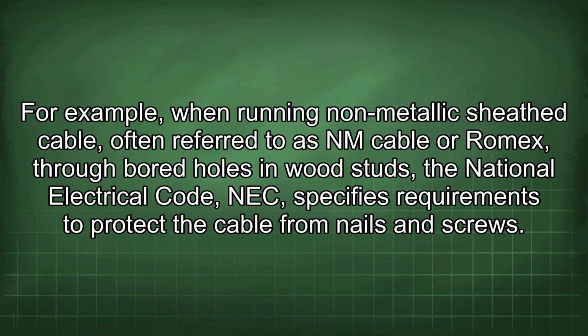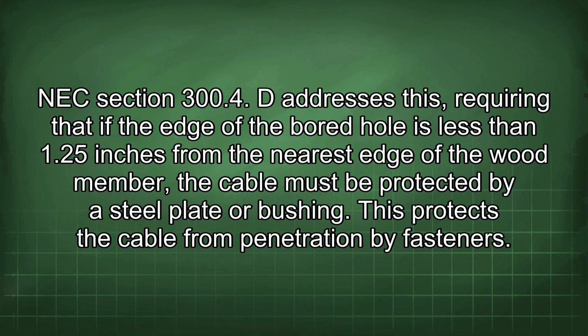For example, when running non-metallic sheathed cable, often referred to as NM cable or Romex, through bored holes in wood studs, the National Electrical Code, NEC, specifies requirements to protect the cable from nails and screws. NEC Section 300.4(D) addresses this, requiring that if the edge of the bored hole is less than 1.25 inches from the nearest edge of the wood member, the cable must be protected by a steel plate or bushing. This protects the cable from penetration by fasteners.